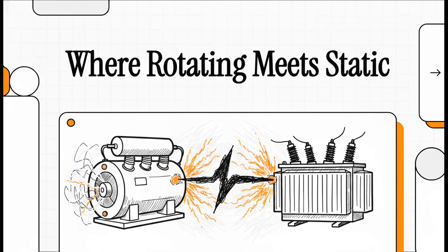Welcome to This Explainer. Today, we're tackling one of the absolute most critical and honestly uniquely challenging junctions in any power plant, where the generator meets the transformer. You see, a generator-transformer block fault doesn't behave anything like your run-of-the-mill transformer fault. Why? Because you've got a massive rotating machine actively pumping energy into the fault for literally as long as it keeps spinning. This rotating to static interface demands the absolute fastest, most sensitive protection in the entire plant. So let's look at why your standard protection philosophy just isn't going to cut it here.